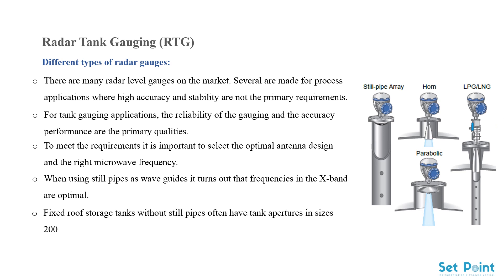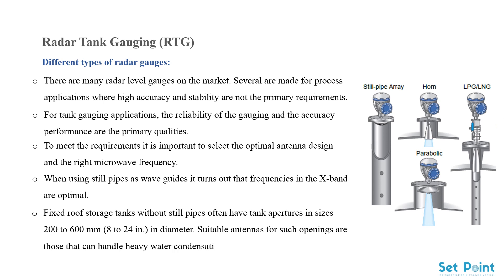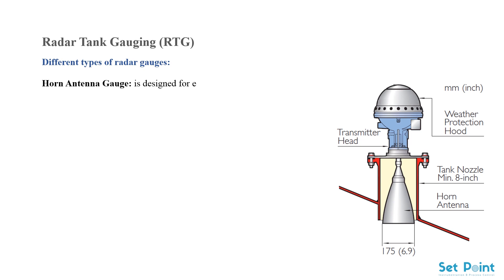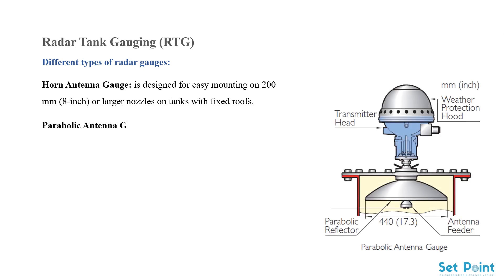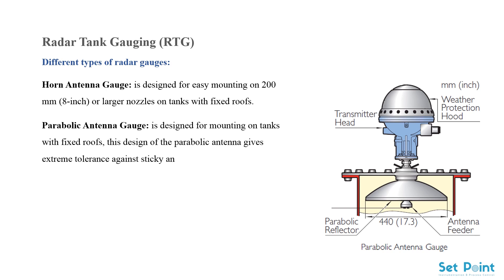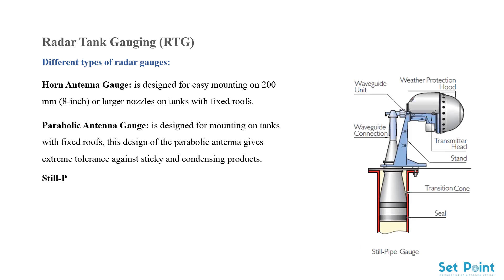Fixed roof storage tanks without still pipes often have tank apertures in sizes 200 to 600 millimeters (8 to 24 inches) in diameter. Suitable antennas for such openings must handle heavy water condensation and dirt buildup. The horn antenna gauge is designed for easy mounting on 200 mm (8 inch) or larger nozzles on fixed roof tanks. The parabolic antenna gauge is also designed for fixed roof tanks and offers extreme tolerance against sticky and condensing products.